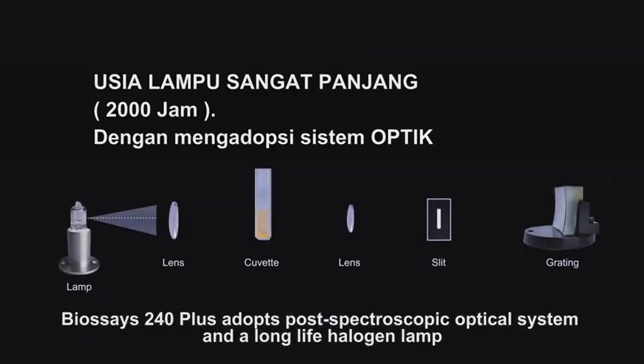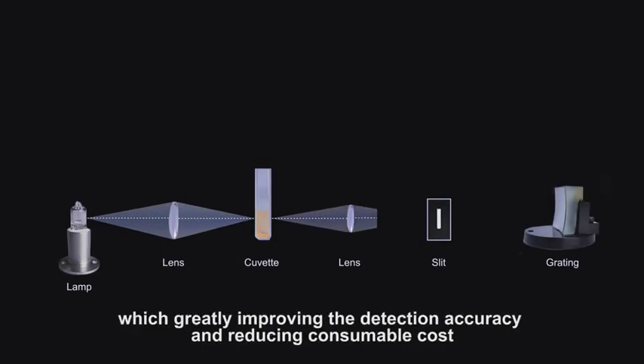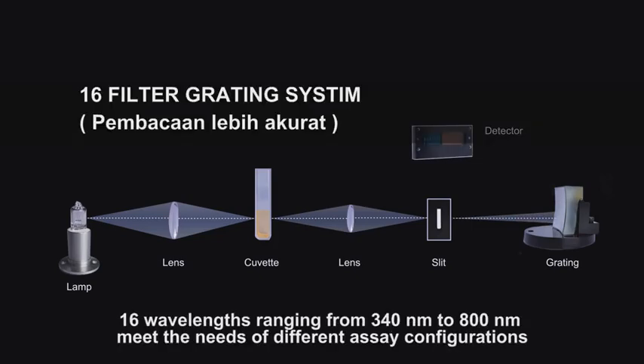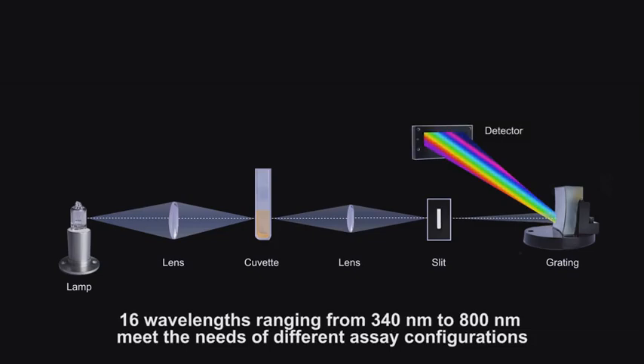Biossays 240 Plus adopts a post-spectroscopic optical system and a long-life halogen lamp, which greatly improves detection accuracy while reducing consumable cost. 16 wavelengths ranging from 340 nanometers to 800 nanometers meet the needs of different assay configurations.